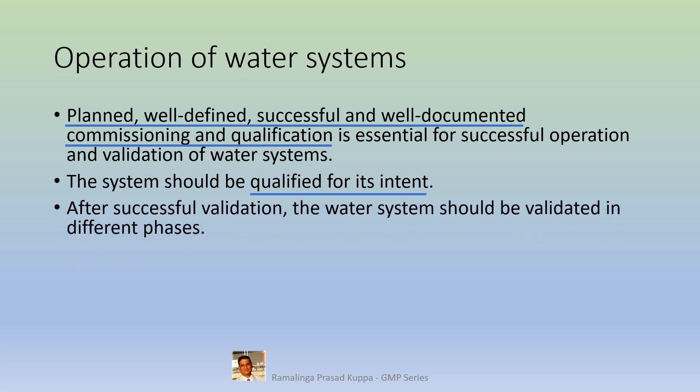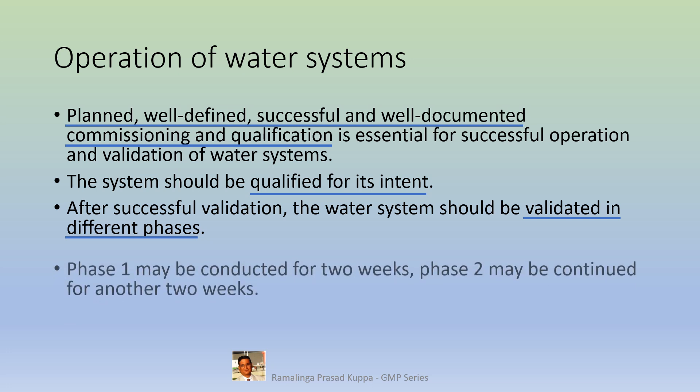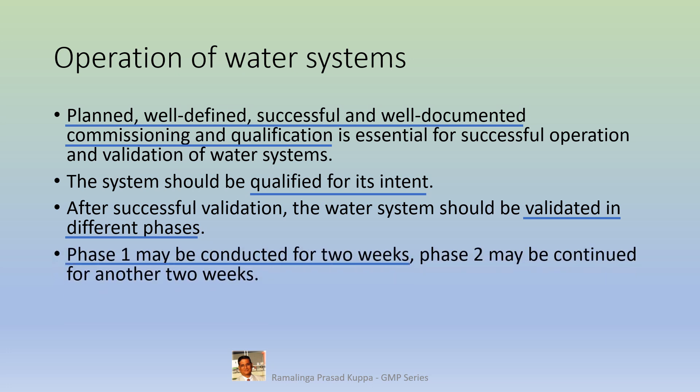After successful qualification, the water system should be validated in different phases. This is the part of performance qualification. Phase 1 may be conducted for 2 weeks. Phase 2 may be conducted for another 2 weeks.